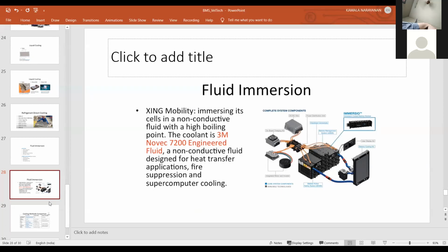Additionally, the flame-retardant nature of the fluid acts as a safety feature, suppressing thermal runaway events before they propagate between cells, because a thermal issue with one cell can propagate to others. Such a problem will not occur when using the fluid immersion technique. A key consideration is the choice of the coolant fluid, determined through primary research.